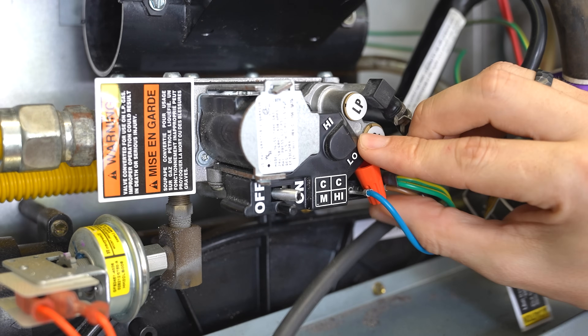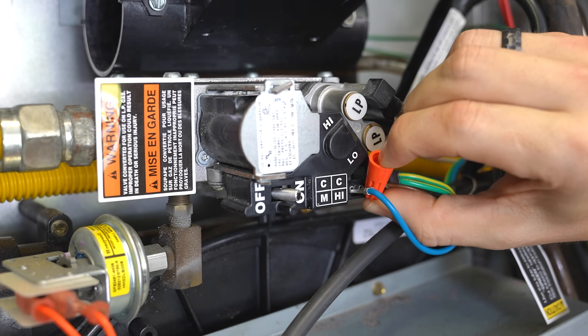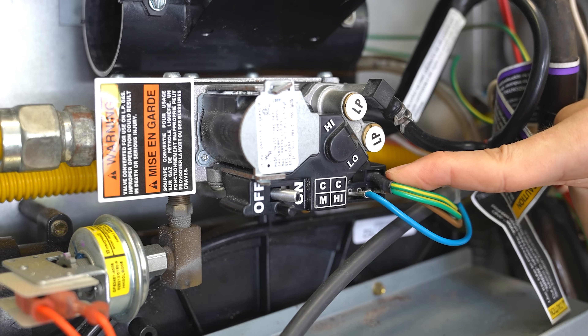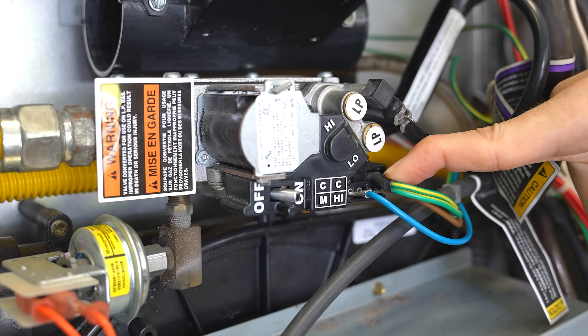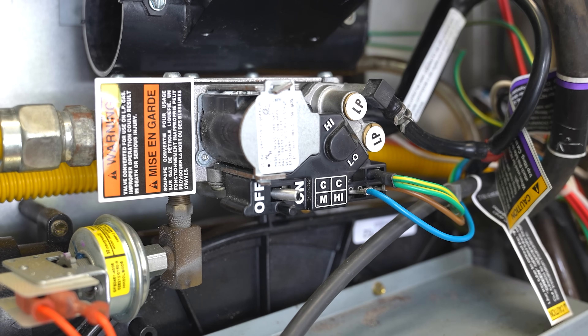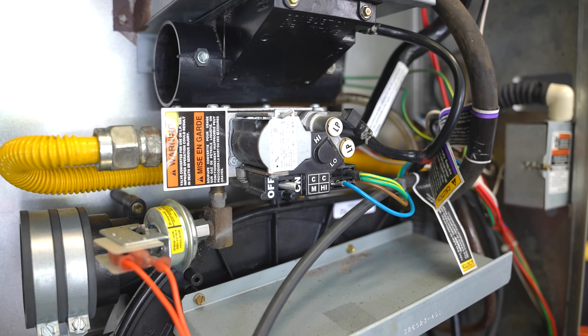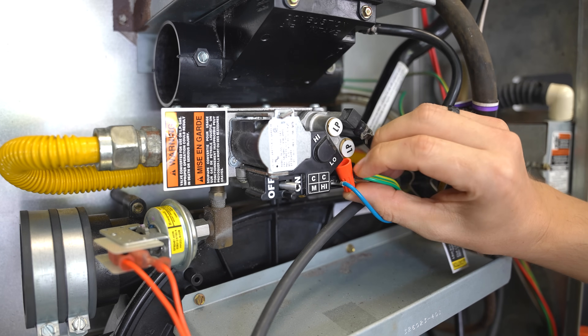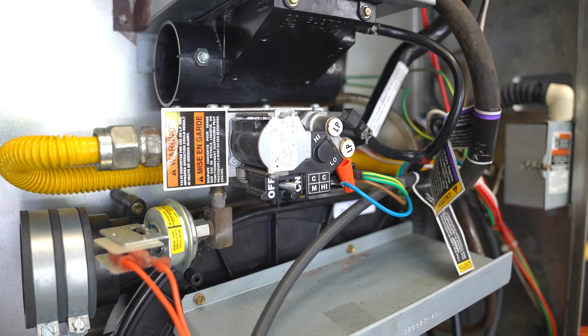I've had plenty of times where the igniter starts to glow, and if I just put my finger on the wire and hold it, the gas valve opens up and everything runs just fine — but right when I let the wire go, everything shuts off. So if you're able to find the point of the loose connection and fix it, wonderful. If not, you can try wedging something in. And if that's not working either, then your only option is to replace the gas valve.